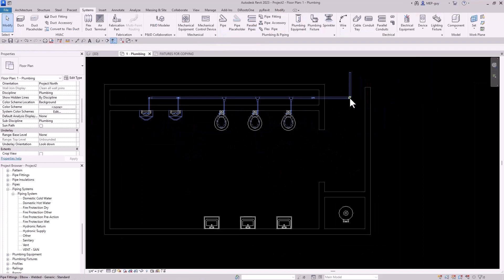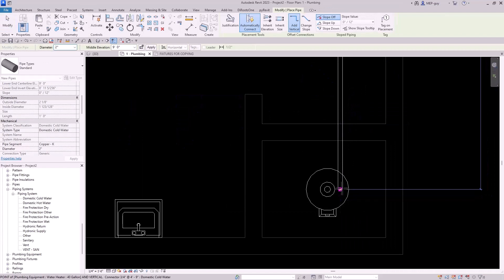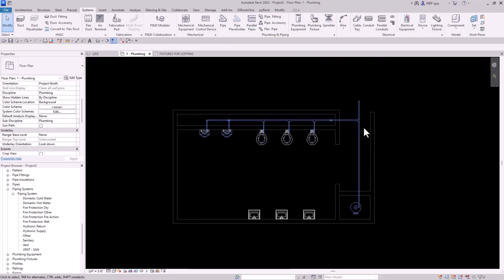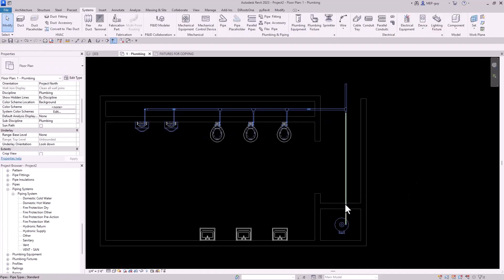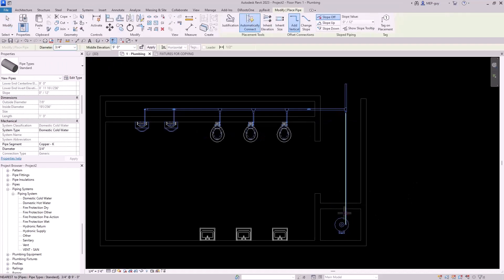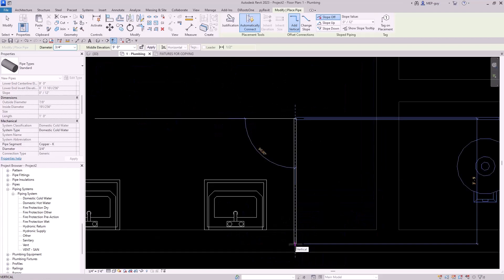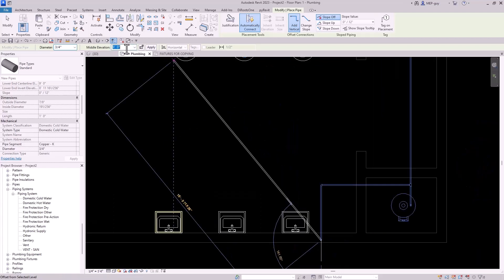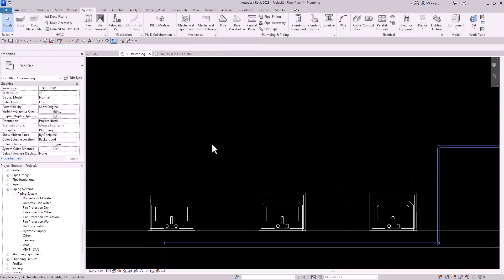Now I'm going to continue in this direction. I'll hit plus, right click, draw a pipe, and draw it into this water heater. I'll update this pipe size to three-quarter inch. Continuing to draw our cold water pipe using the create similar command — we'll go from a point here, drop down in the wall, go to one foot, and go off to this side. We'll line up with the connector and it's going to snap. Hit escape.